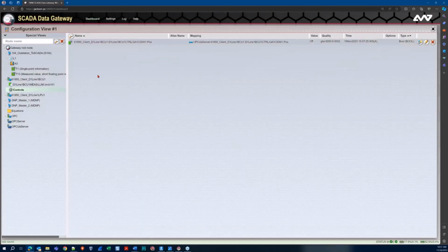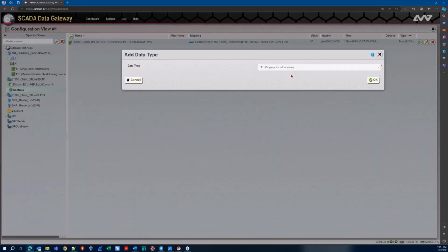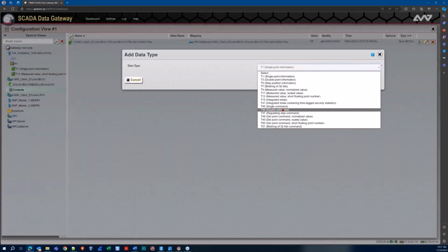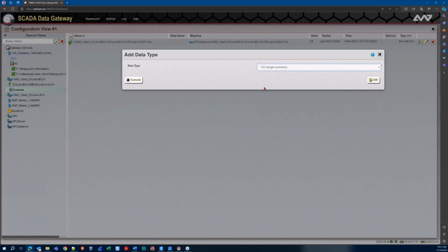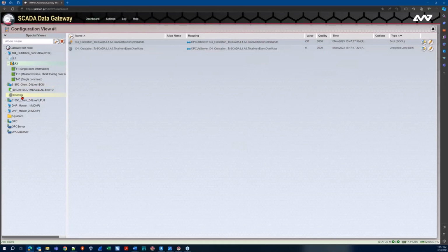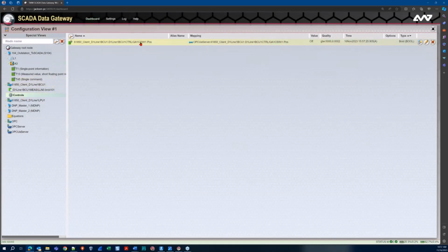So now I've brought the control into the gateway. I need to map it to the equivalent place on my 104 side to make sure it's available from SCADA. To do that, I just need to right click and add the appropriate data type. I alluded to it earlier, but T45, our single command, will pair nicely with this select before operate position value. Just hit OK. And then now I come back down to my control and click and drag that point up there.